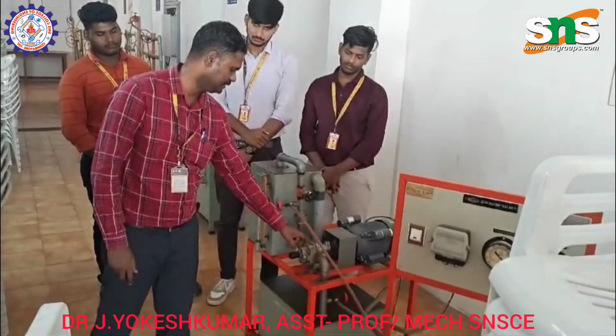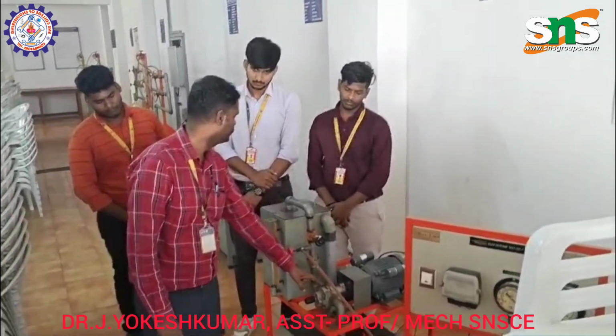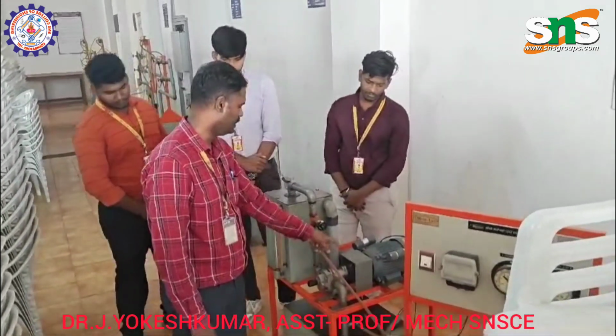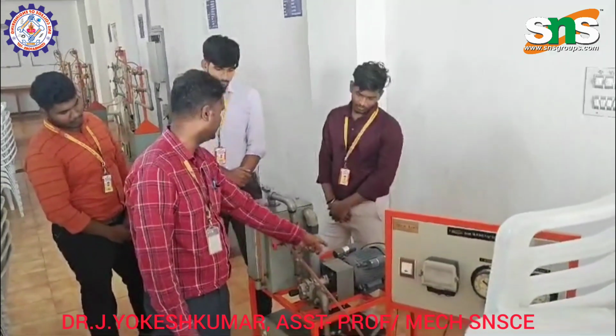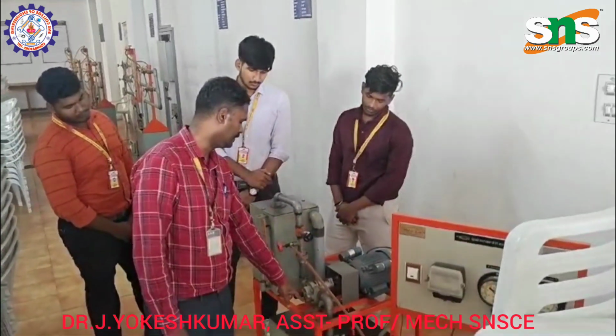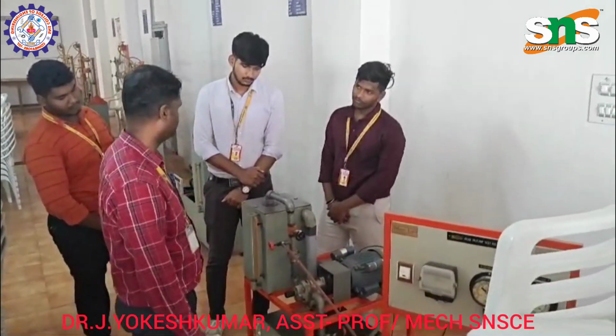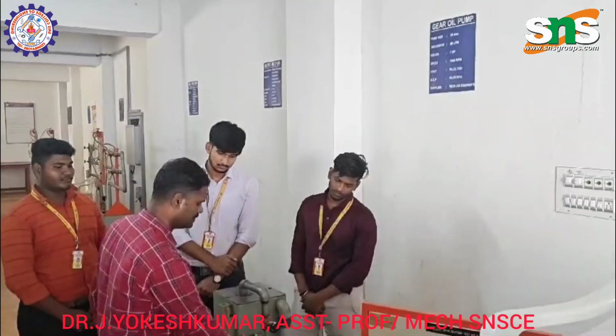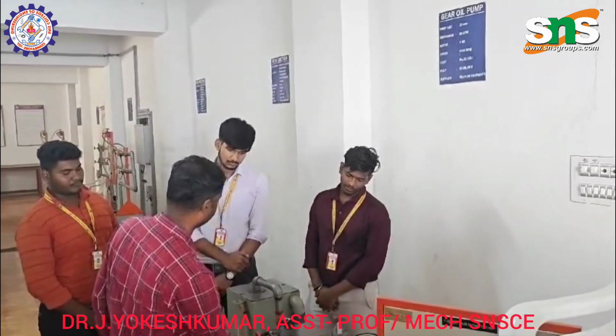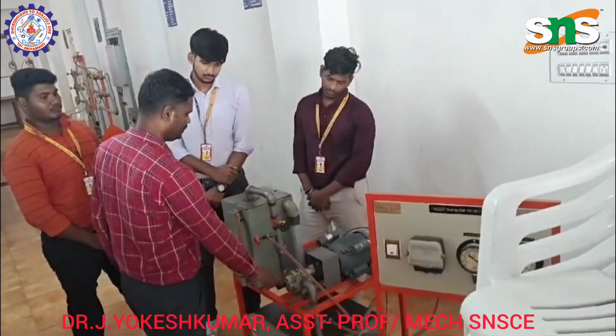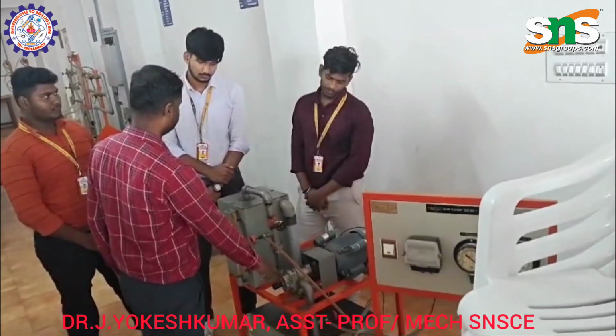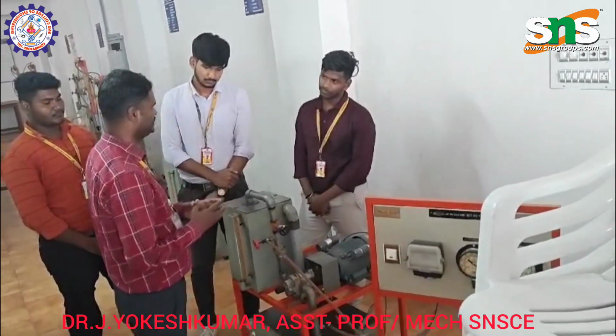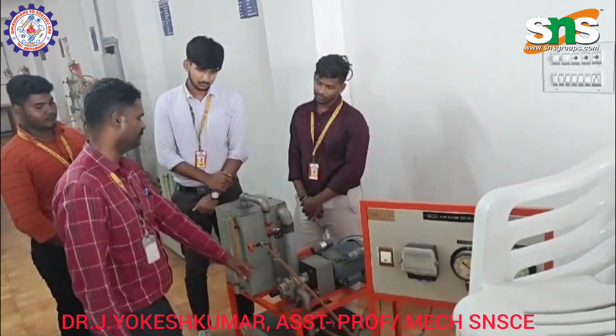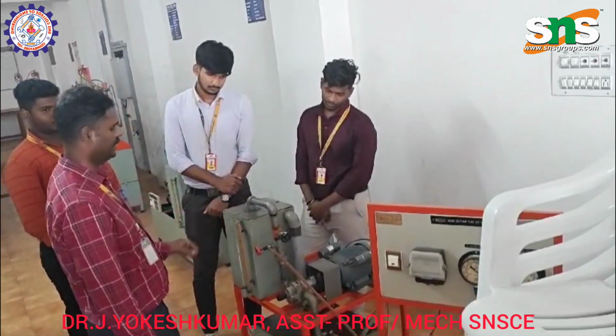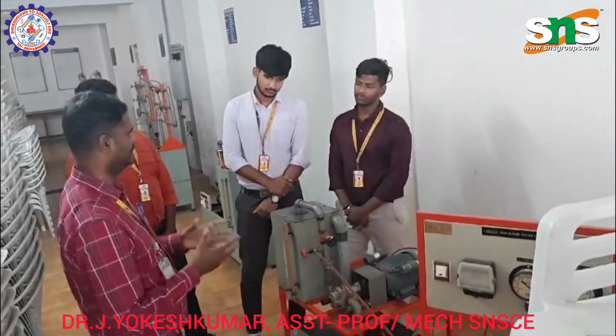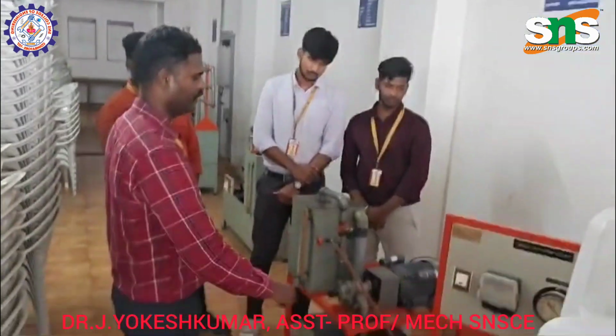For example, the rotation is counterclockwise on this side. When you rotate this gear, because it is connected with the motor in a counterclockwise direction, the other gear will rotate in a clockwise direction. Both will cause unmeshing. Unmeshing increases the volume and it will take the fluid from the reservoir. Then it is carried by means of the teeth, and finally we have meshing on the opposite side. Meshing reduces the volume, so the fluid is pressurized, and the pressurized fluid is sent into the overhead tank.